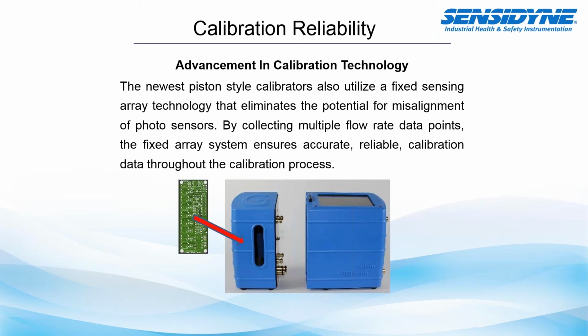A more sturdy solution is a fixed array system, which cannot become misaligned. It can also provide additional data points, as a fixed array system can have more than just a start and stop. It can actually measure the movement along the whole fluid travel of the puck in the cylinder itself.